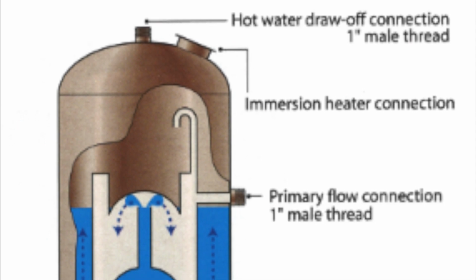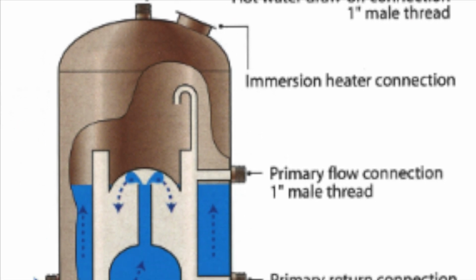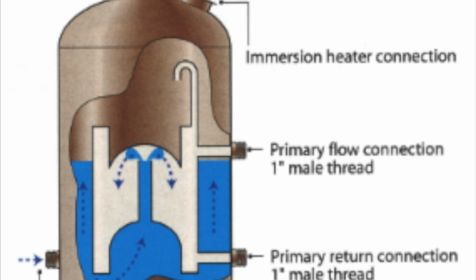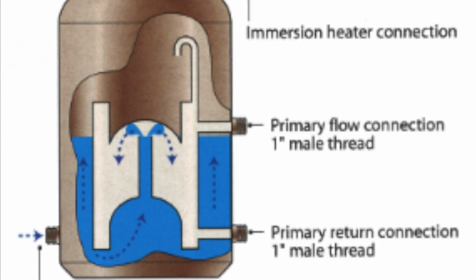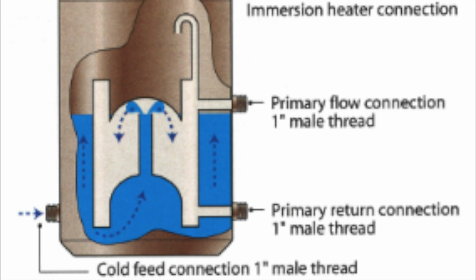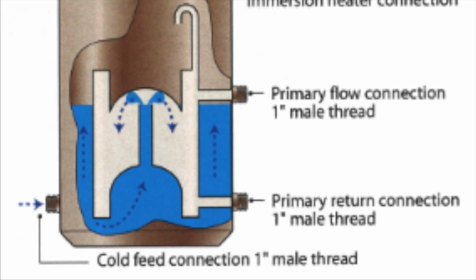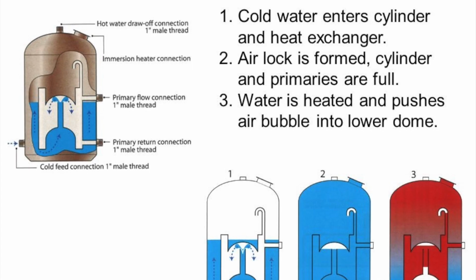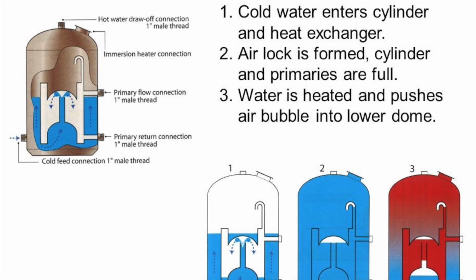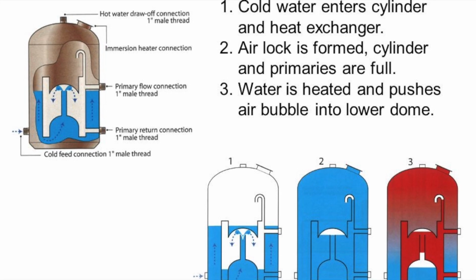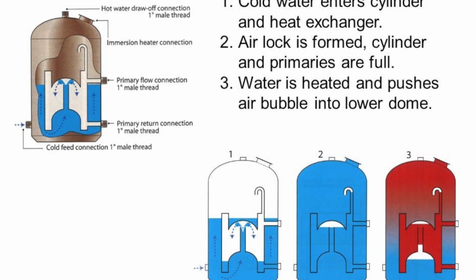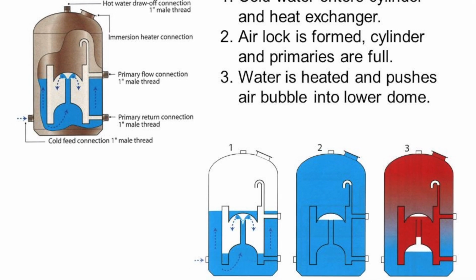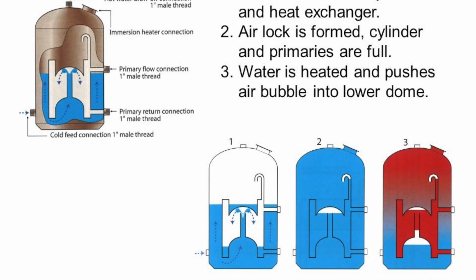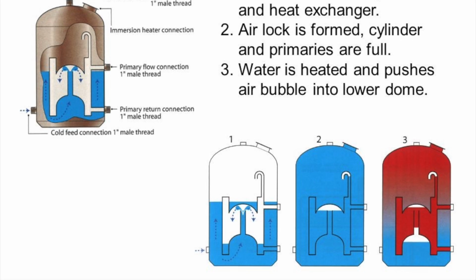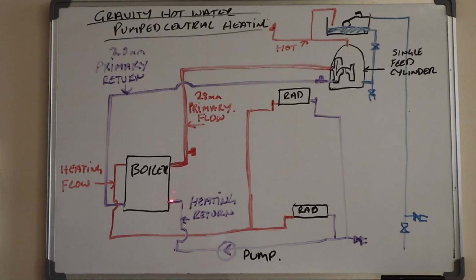Also, if you try and put a pump on the primary flow to a PRIMATIC cylinder, it will damage the bubble. Also, if you try and turn this gravity hot water pump central heating system into a fully pumped system with a PRIMATIC cylinder, you will also damage the bubble. So with a PRIMATIC cylinder, they can only go on to gravity hot water pump central heating. So there's the return going in.